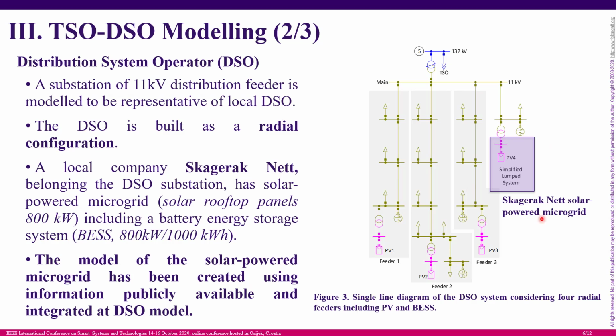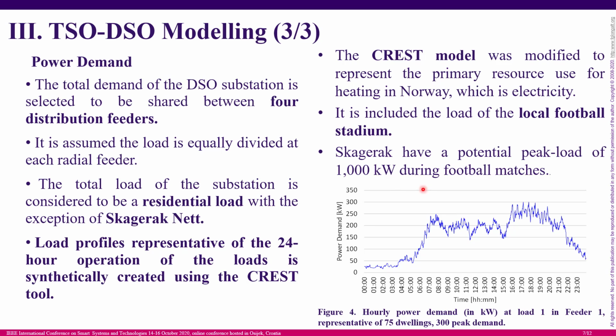This is like a small microgrid inside the distribution system and a place that we can use for voltage control for the local DSO. The demand in this system has been created using 4 different distribution feeders, combining residential load and the Skagerak Nett load. Okay, the analysis that we are performing here, the assessment, is based on 24-hour operation. As a consequence, we need a load profile for 24 hours.